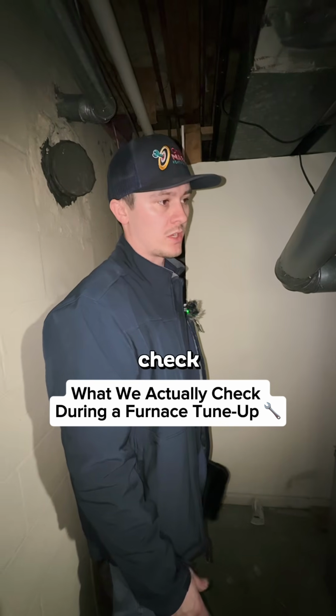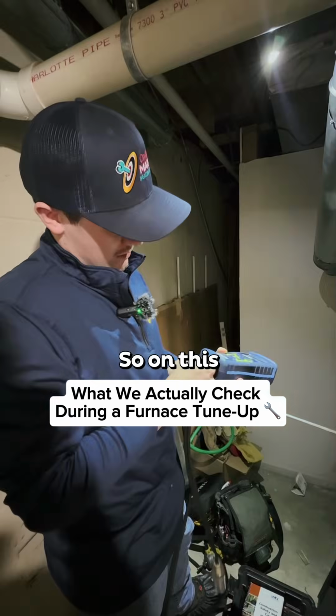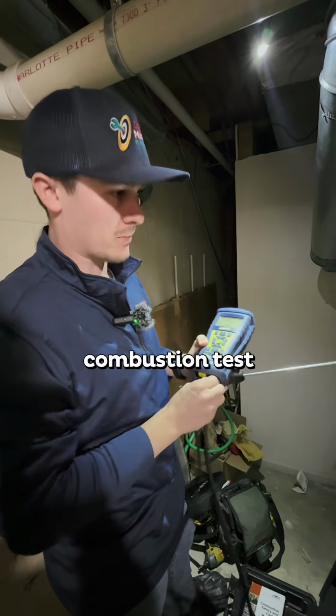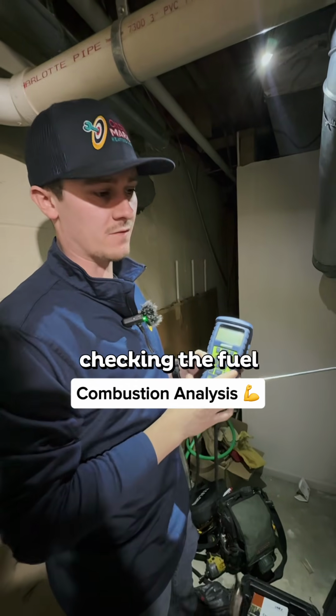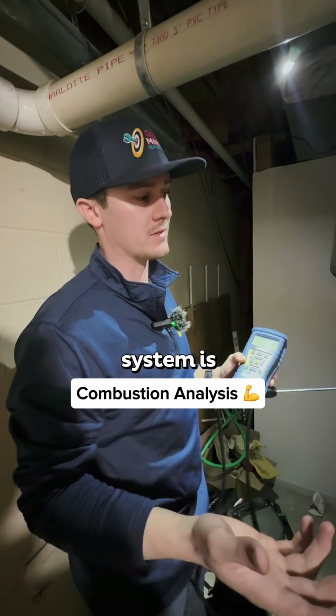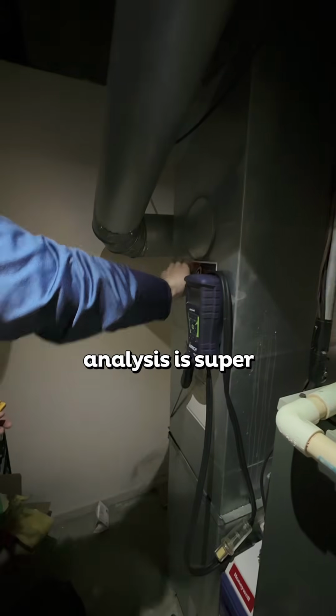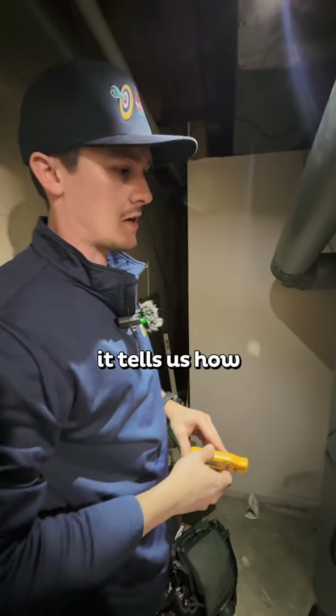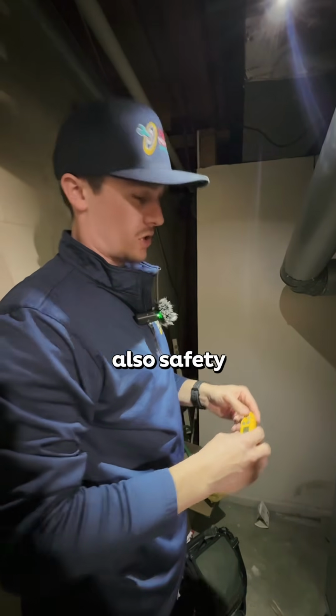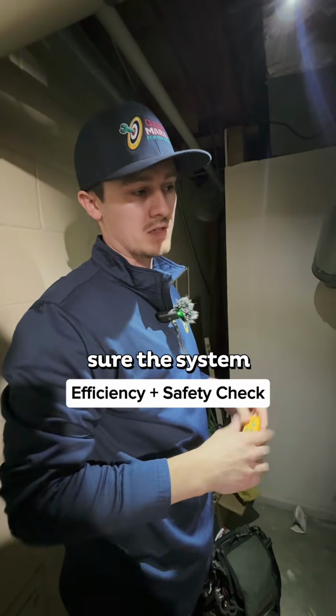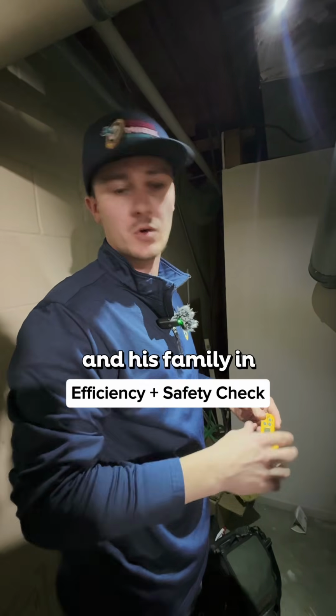We're going to jump into the tune-up and just check everything out, make sure it's all running properly and running safe for them. So on this specific system, we're going to do what we call a combustion test. This is essentially checking the fuel and oxygen mixture that the system is making while it's creating combustion. So combustion analysis is super important because it tells us how the system is running from an efficiency standpoint, but also from a safety perspective as well. We want to make sure the system is running safely for our customer and his family and his home.